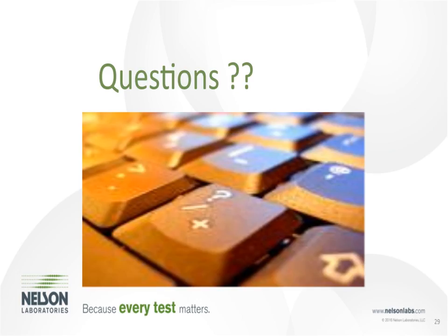Another good question. So this would be a classic example of an indirect contacting device. So let's say that's a vascular drug, then you would be an external communicating device, blood path indirect, because what chemicals could come from your device into that drug, leach into that drug, and then be delivered to the body. So yes, even though you don't have that direct patient contact, you would have indirect patient contact through that drug. So a risk assessment should be performed for that type of exposure.